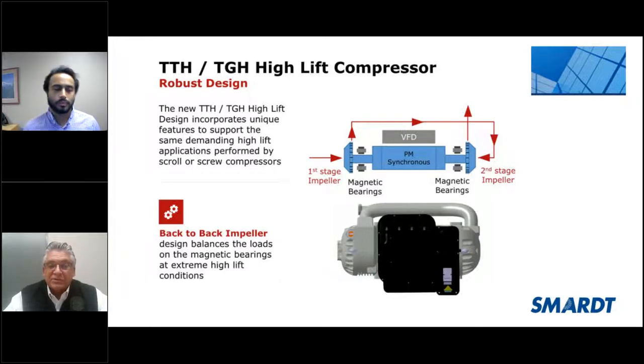And if you look at magnetic compressors, the impeller and the shaft are actually levitated, right, by magnetic force. With one impeller, it would actually move that impeller back towards the other end of the bearings and would have a little bit of an issue with performance. So now having two impellers opposed to each other, the load's balanced, and now you have the high lift, high differential pressure is no longer an issue. Great approach, great technology, done a good job of meeting that need of high lift and low load capabilities. I'll stop here. Any questions on that at all, guys? Hopefully that makes sense.